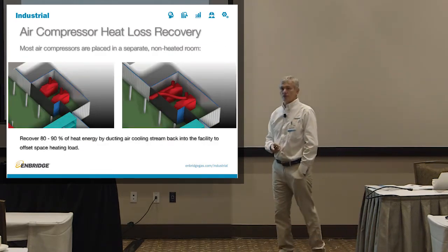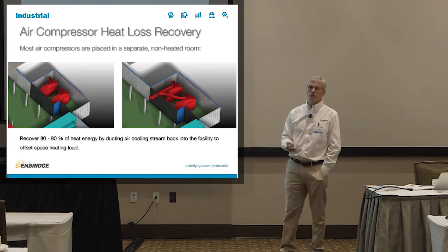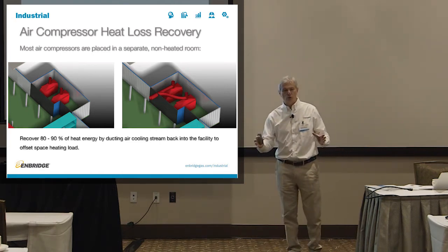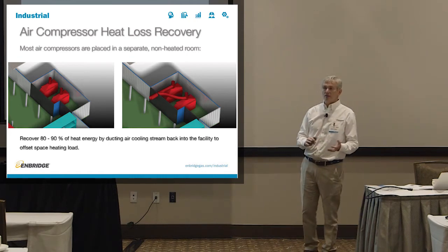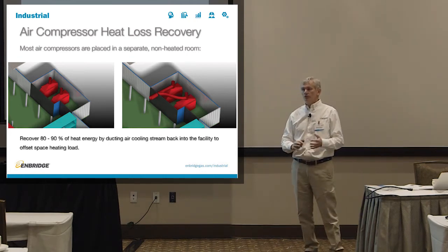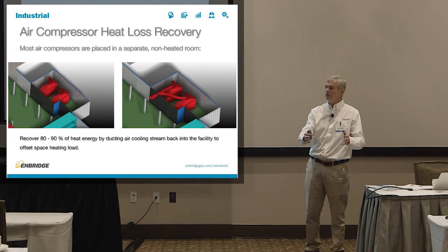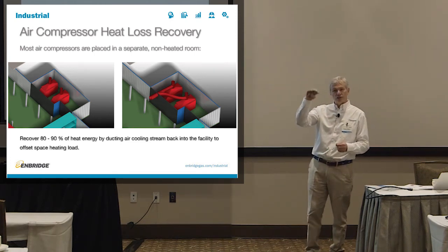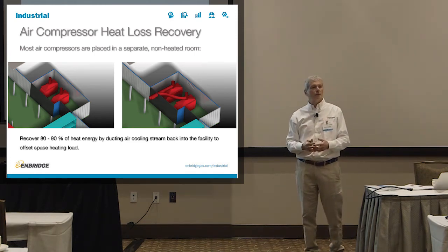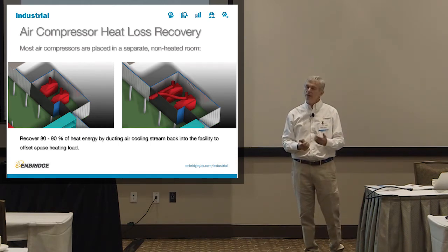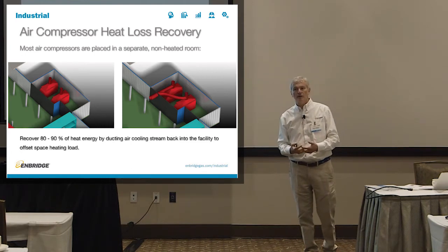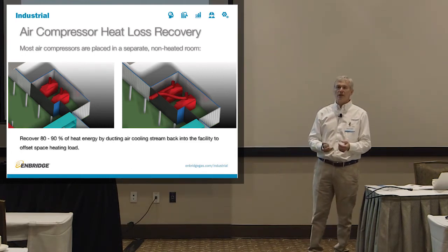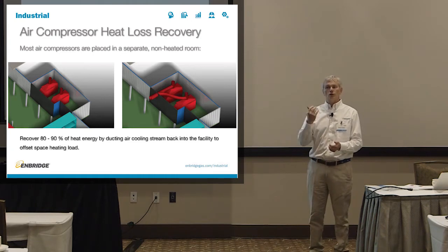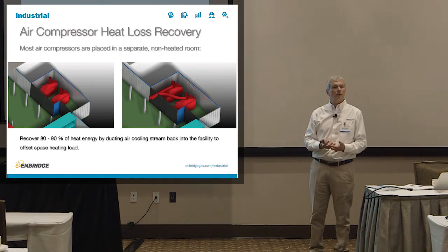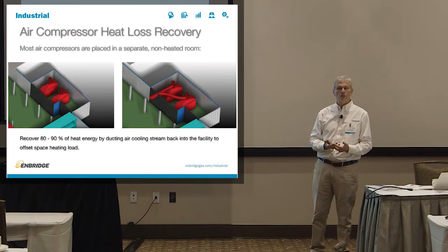What about air compressors? We all know that air compressors usually sit somewhere in a little room because they're noisy, and oddly enough, they're hot. So we put them into a room on the side of the facility, we close the doors, we put shutters, and we put openings into that room so we can get cold air in, because compressors like to run with colder air. They don't like hot air. And secondly, we put a big exhaust fan above them to exhaust all that heat, because they're really hot if you enclose them in the room.